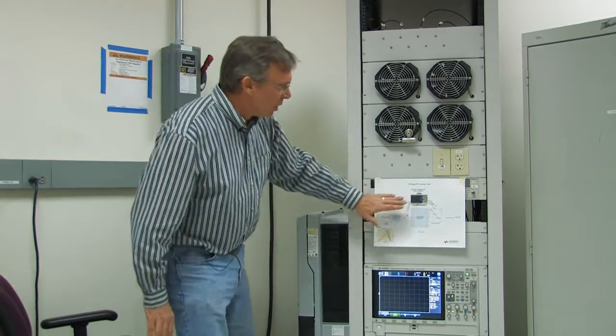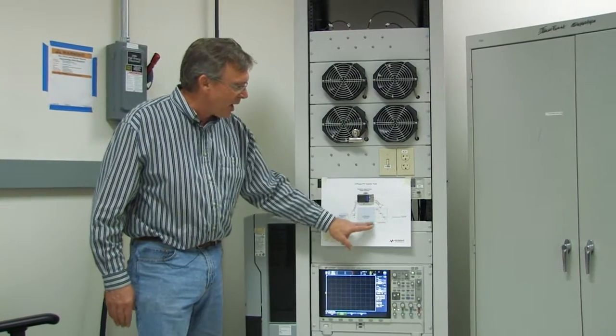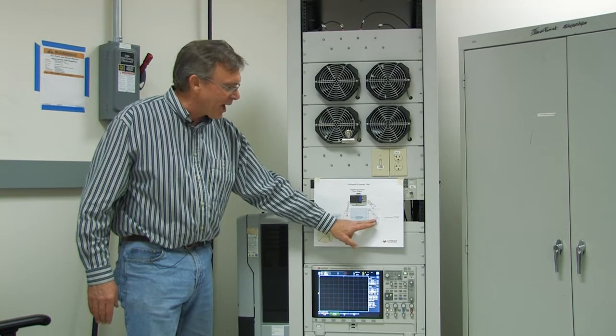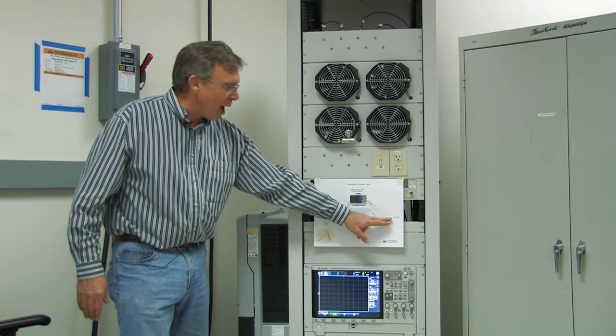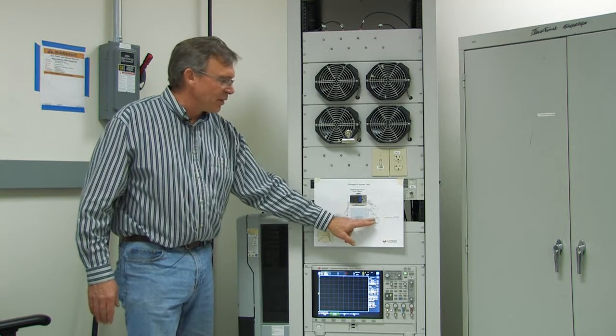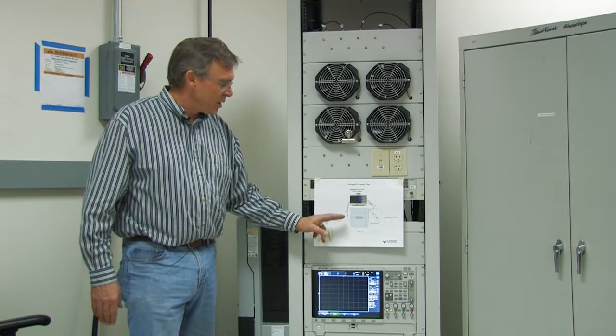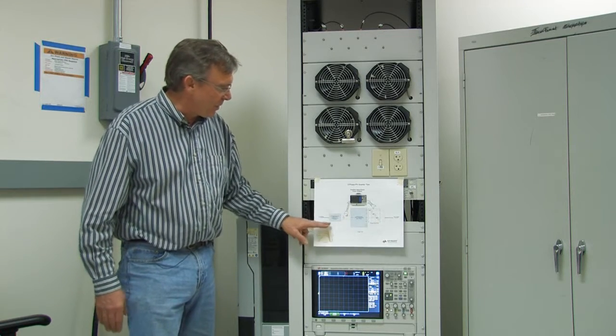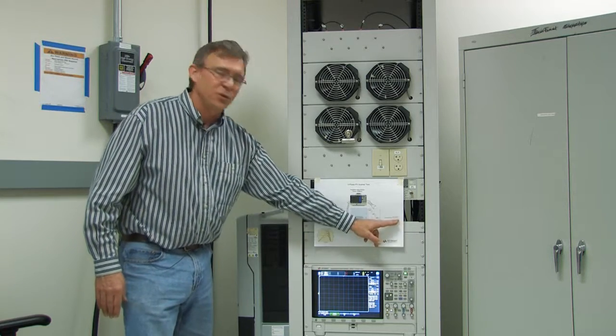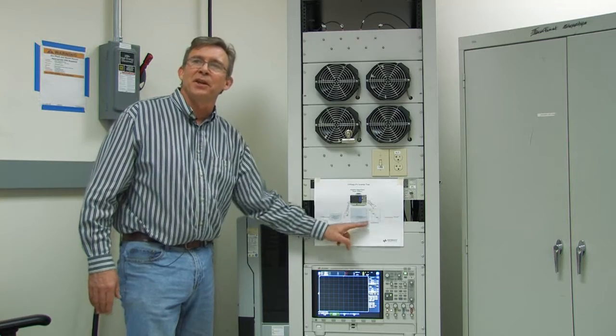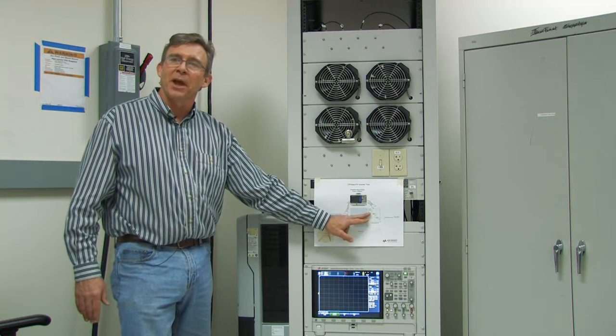The one thing I might note here on my wiring conventions is because I'm using a standard breakout box, I've defined the power as being delivered from the wall. So positive power would be coming out of the wall. Because the power flow through our test system is from the 208 to the 480, I should expect to see negative power as measured on our input group.